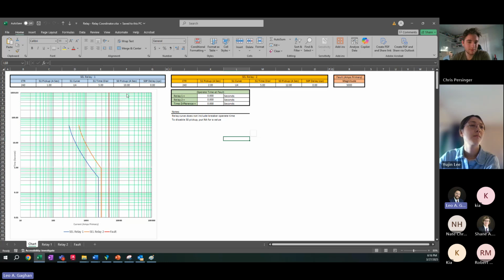So if you play around with this stuff, you could increase your instantaneous element, your time dial, all these different things to get different results. A quick one, right? If I were to change this fault current, let's say to 2000 amps, you see how that moved over? Well, we went out of that instantaneous region, and now we're in that inverse time. And we can see relay 1 now operates in about a half second. Relay 2 operates in about 2 seconds, and there's our time difference.